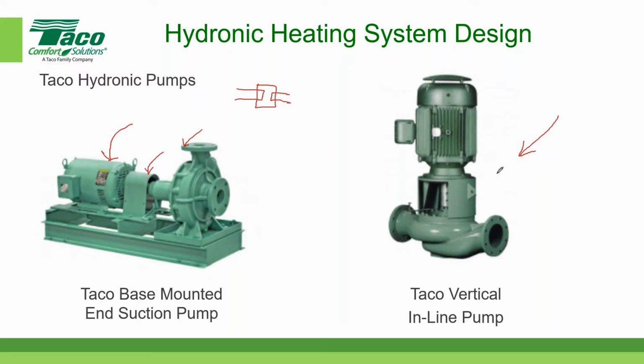And the one that we've shown here in this photograph on the right is called a split coupled pump. Now you can't really tell unless I point it out to you, but we have a similar situation where we have a motor shaft. In this case, the motor is oriented vertically, and then we have a pump shaft. And then those two shafts are connected through a machined coupling. So the coupling for the end suction pump is a flexible coupling, but in this case the motor, the adapter and the pump all are connected through what we refer to as machine fit.